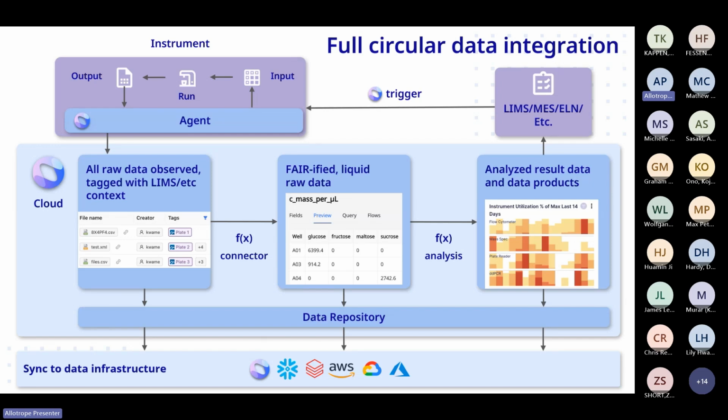We will actually take that out with the context, load a plate map or work list or a configuration file onto the instrument, and that's how we encode that sample ID or batch ID in. We, through our agents, will write that file in, instrument consumes it, runs it, and then whatever output has that will have that sample ID going through. So when we capture the data and then parse it into FAIR data, ideally in Allotrope, and then analyze it down and put it back, we already know where it needs to go, and we've established that sample lineage.